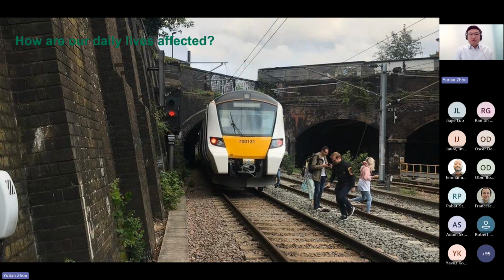And a major contributor, and in my own opinion a bit of a disappointing point, is a disruption to a particular class of trains that operates in the southeast area of the UK. Approximately 60 trains unexpectedly shut down when the frequency dropped below 49 Hz, and half of those trains required a visit from a technician to get restarted. So this caused major issues within the rail system, and that really caused a lot of the hazard.